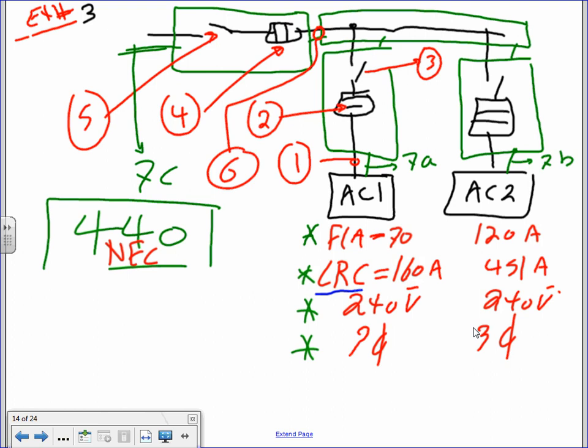There are two chillers or two AC units or two rooftop units. What's special about them? They have a sealed compressor, and when they have a compressor, the code treats them slightly differently and assigns Article 440. We need to size the branch circuit, the fuse for the branch circuit, the disconnect for the branch circuit for both of them, the feeder, the fuse, and the disconnect for both units.